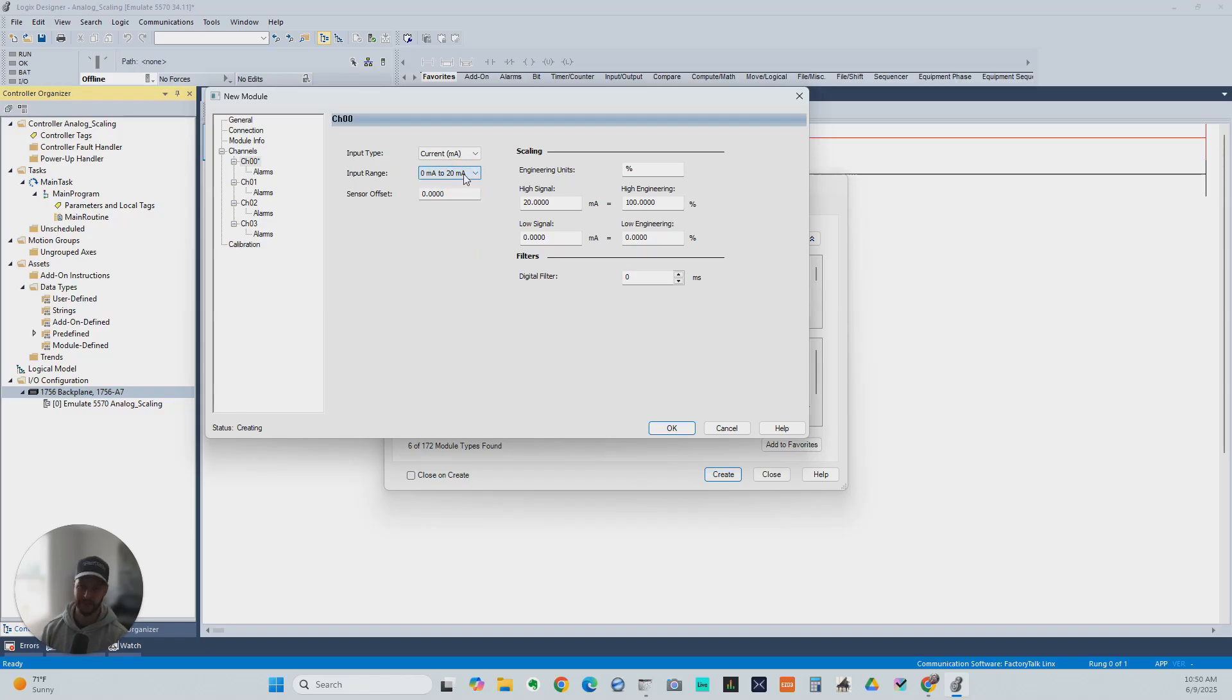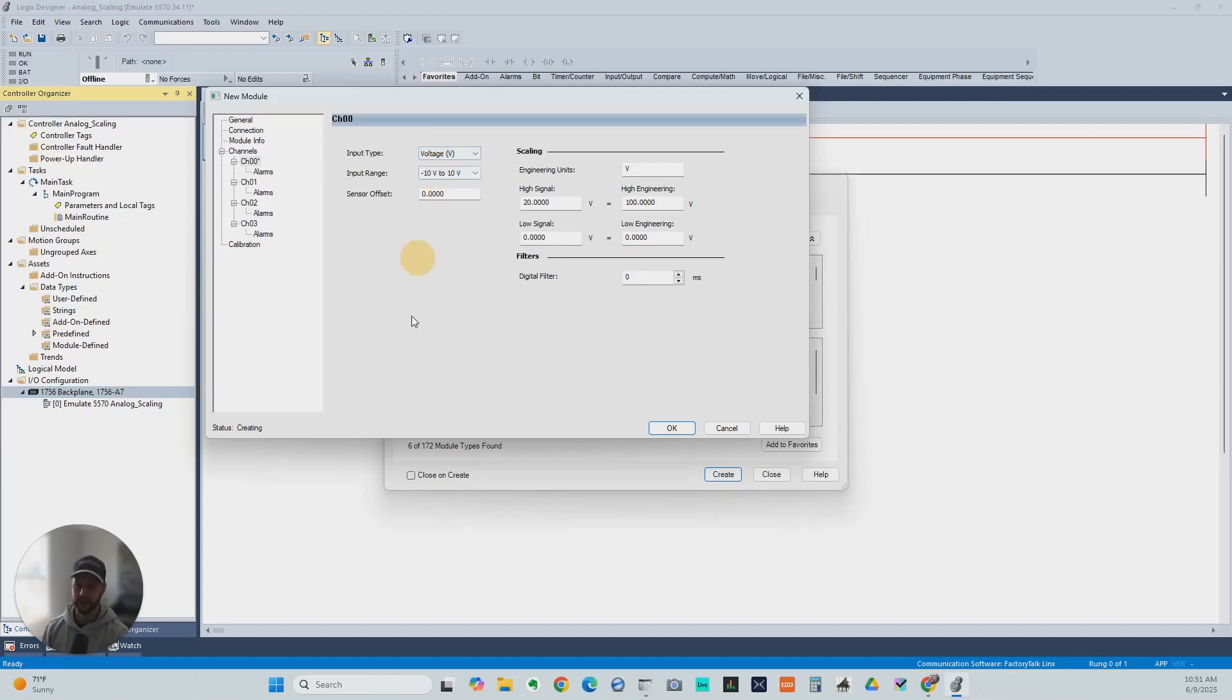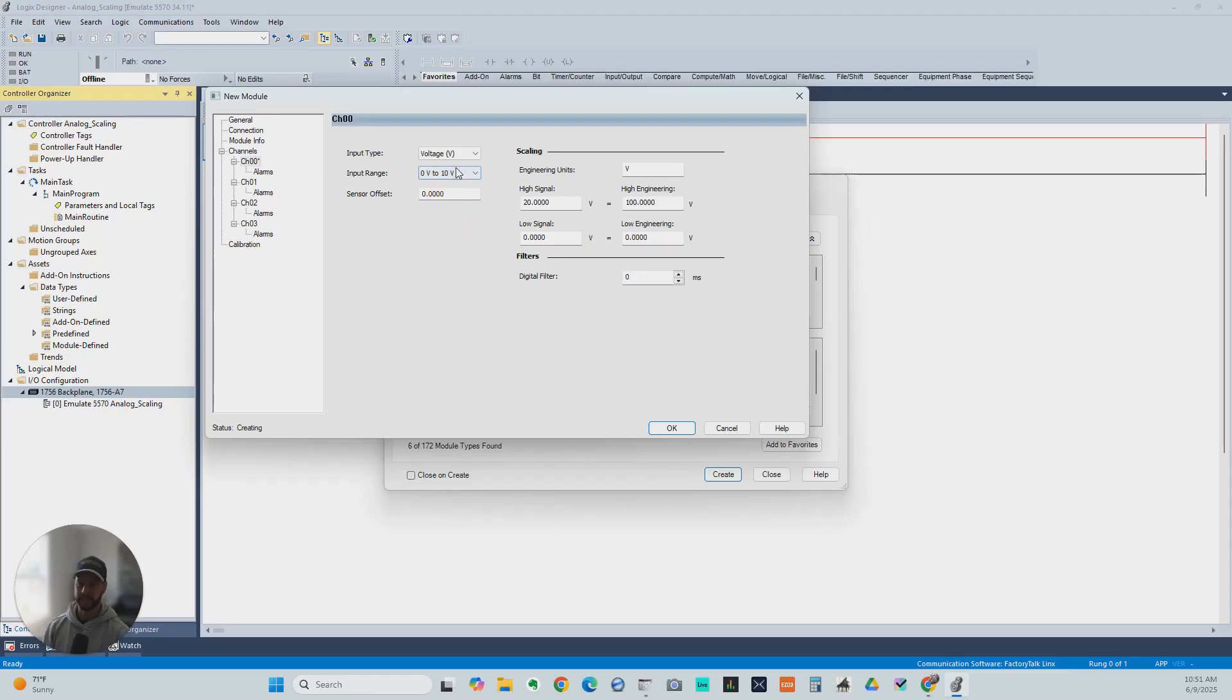It's 0 to 20 milliamp, but you can use a 4 to 20 milliamp input because that's within that range. That's something we can talk about in more detail another time. But let's just go with a voltage signal for now. Keep it as simple as possible. We're going to go 0 to 10 volts. So we're going to be looking for a 0 to 10 volt analog input signal.